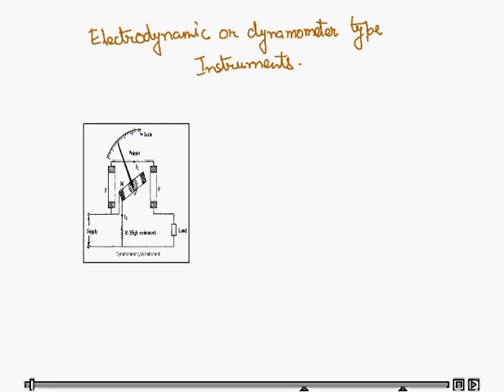We will study about the electrodynamic or dynamometer type instruments. The construction is shown here. First we will discuss the principle. The basic principle of dynamometer type instrument is that when a current carrying moving coil is placed in a magnetic field produced by the current carrying fixed coil, a force is exerted on the coil sides of the moving coil and deflection takes place.